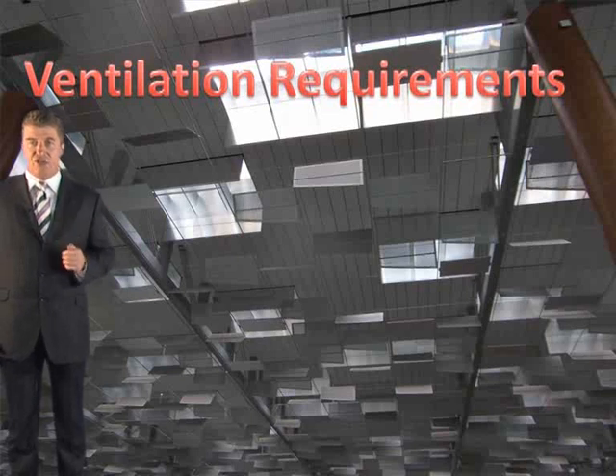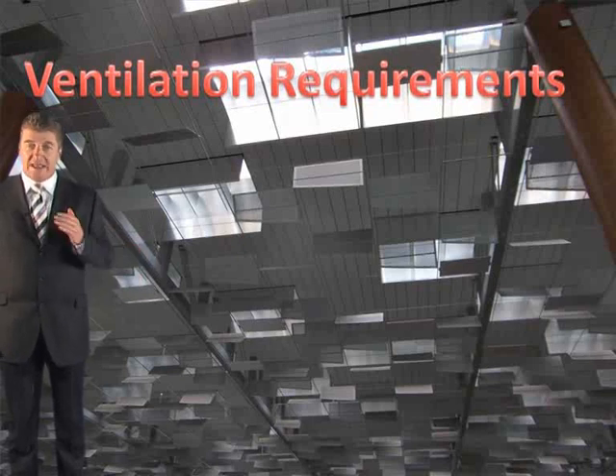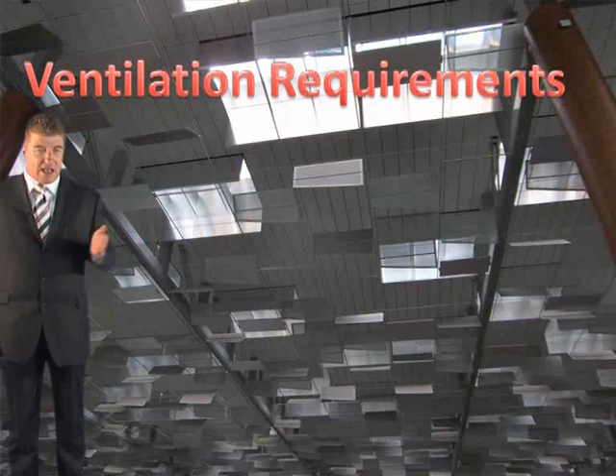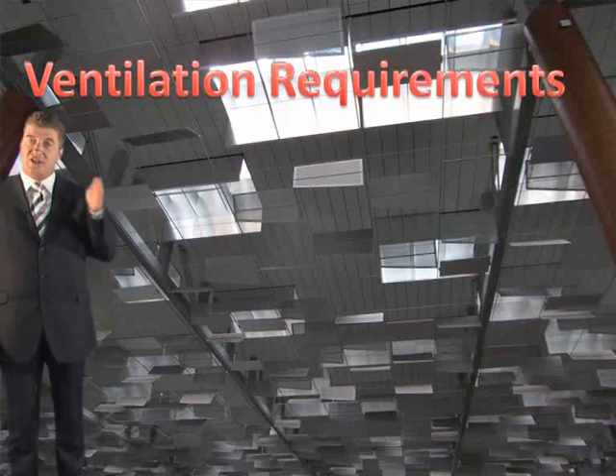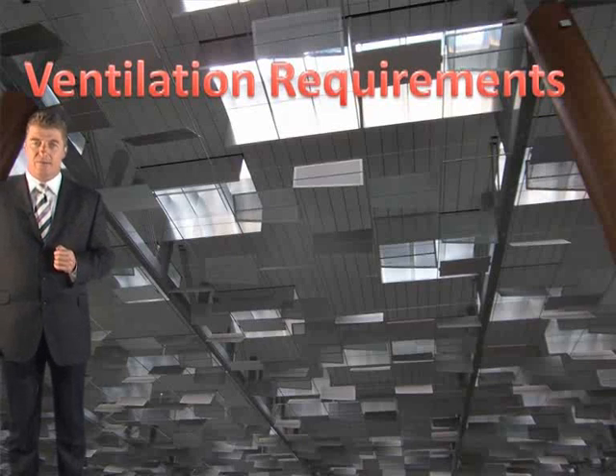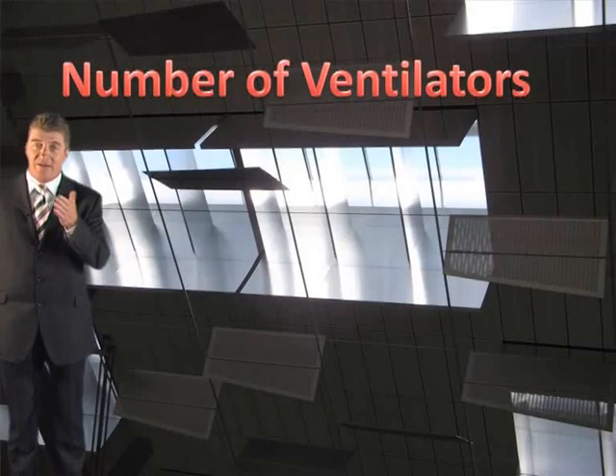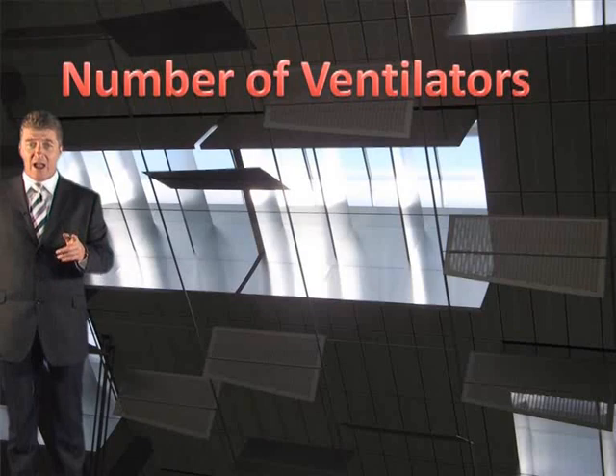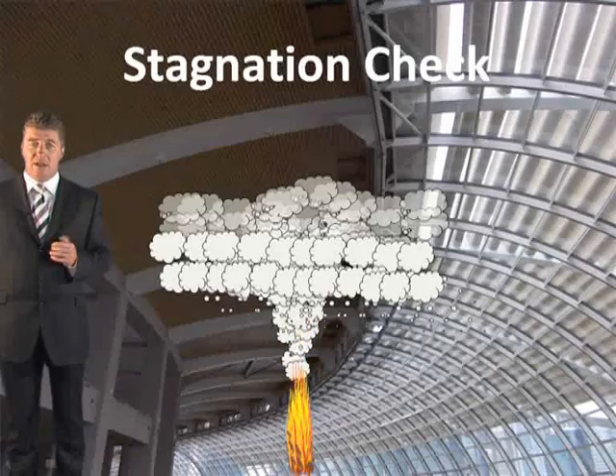V is your ventilation requirements. In this step, you're going to decide which method of extraction you're going to use, whether it's natural or mechanical, and then determine the mechanical or natural requirements. In this step, you'll need to work out the number of reservoirs, the ventilation area, or you've got your volumetric extraction rate. So understand natural and mechanical ventilation requirements, that's what we're going to work through. And you need to now know how many ventilators you're going to need in each reservoir, so that's that step.